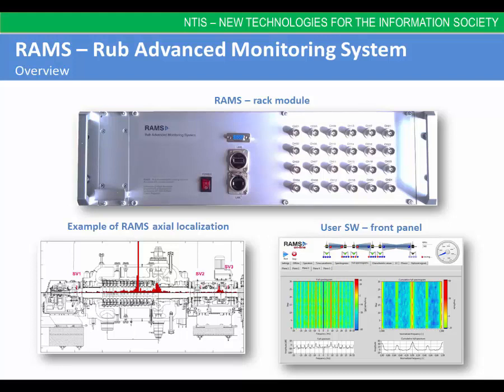The RAMS functionality is based on the fact that apart from the change of the vector of the first harmonic component in the vibration signals, the contact is also accompanied by formation of sub-synchronous spectral components whose frequencies correspond to a number of impacts of the rotor to the stator per rotation period.